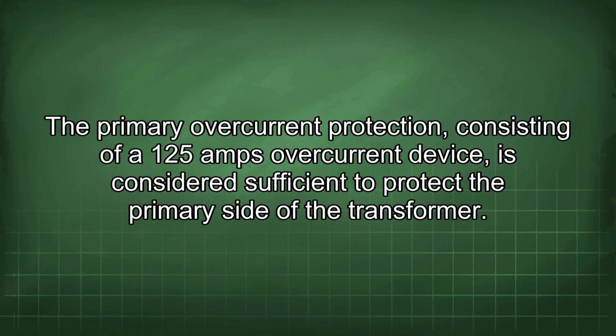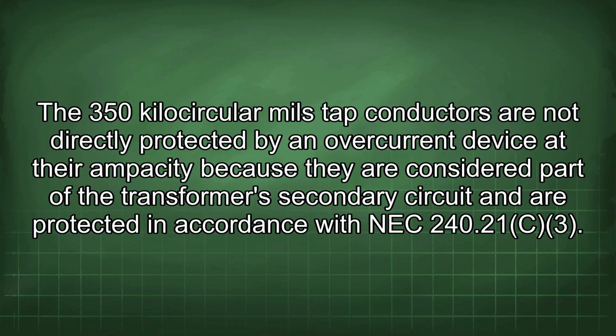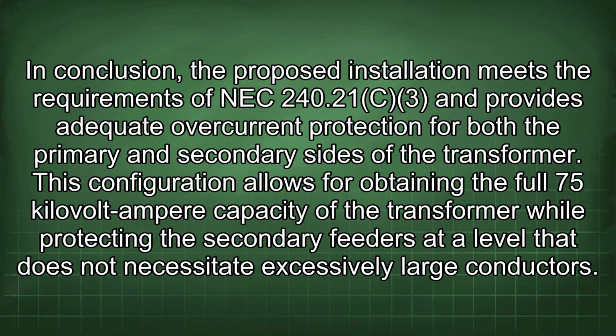the transformer. The 350 kcmil tap conductors are not directly protected by an overcurrent device at their ampacity because they are considered part of the transformer's secondary circuit and are protected in accordance with NEC 240.21(C)(3). In conclusion, the proposed installation meets the requirements of NEC 240.21(C)(3) and provides adequate overcurrent protection for both the primary and secondary sides of the transformer.